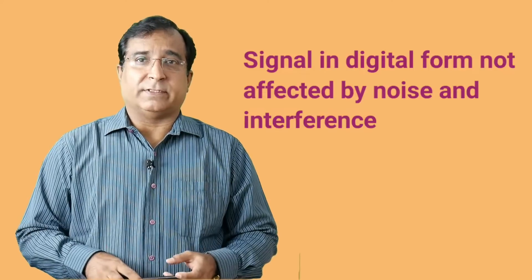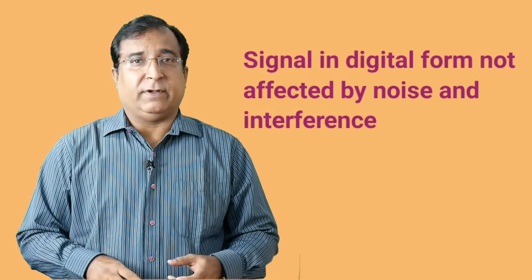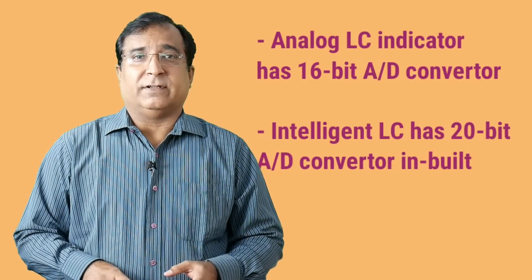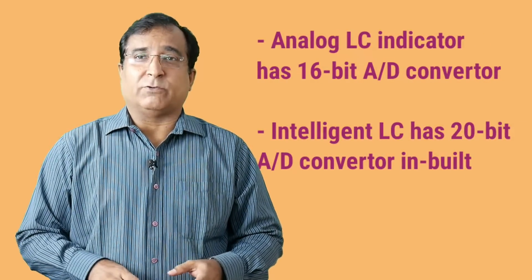As the output signal from the load cell is in digital form, then there is no problem of interference, transient noise in long transmission cable is also eliminated. Typical analog load cell indicator has a 16-bit analog to digital converter by which you get only 50,000 counts or steps.